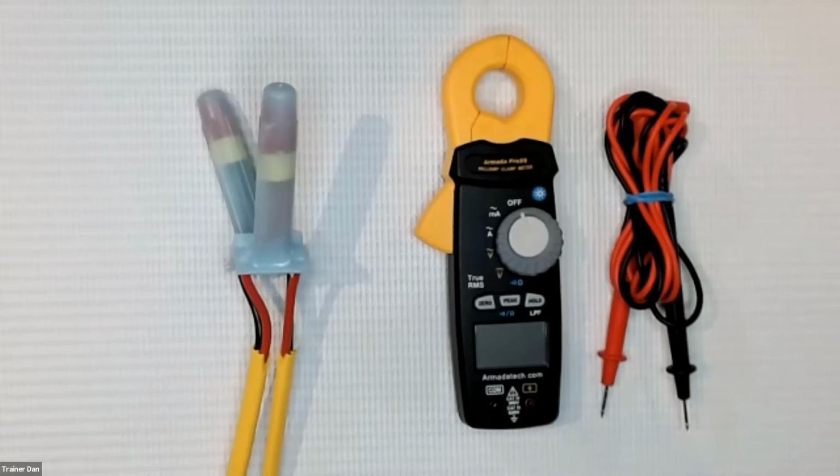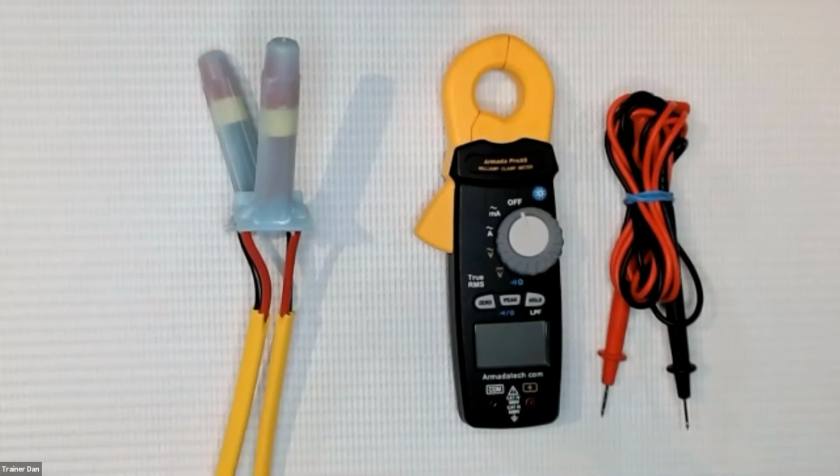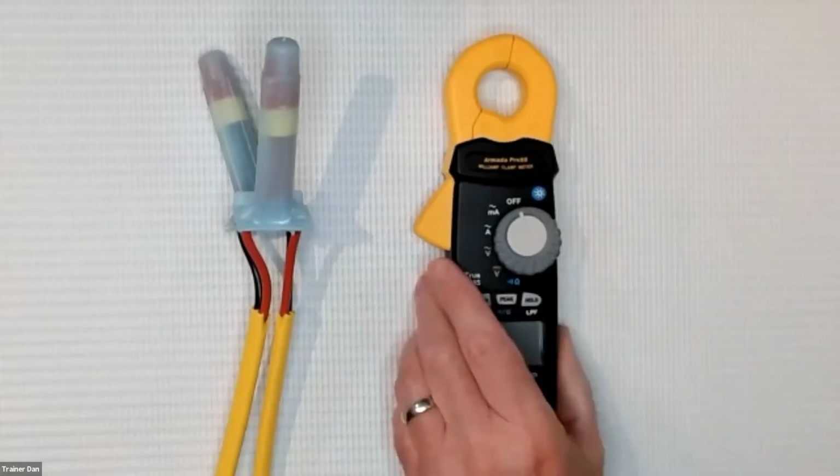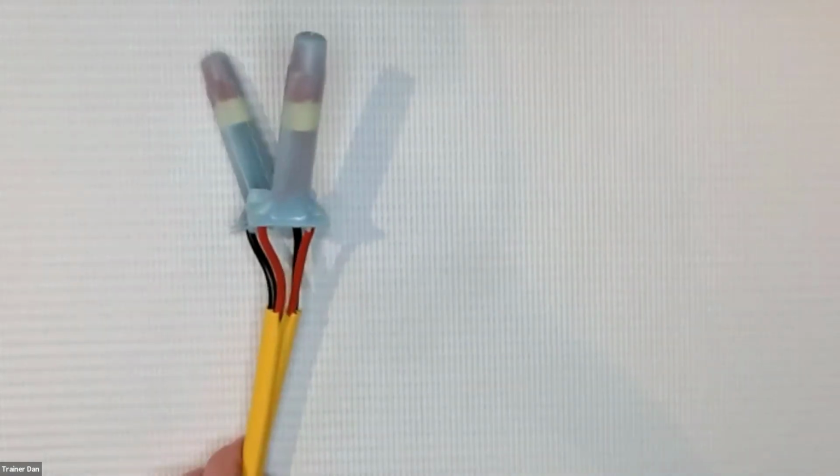Yeah. Because we're not going to go into depth on how to troubleshoot an overcurrent, but these are the tools that are required in order to find a short that exists on the two-wire path. And that short may be caused by a bad connection. It could be caused by a failed device. There are different things that would cause an overcurrent on any two-wire path, regardless of manufacturer. These are the tools you need to do it. Right on. And the video does it. It's pretty detailed. It talks about the tools, what you need, what you don't need, and how to do that.